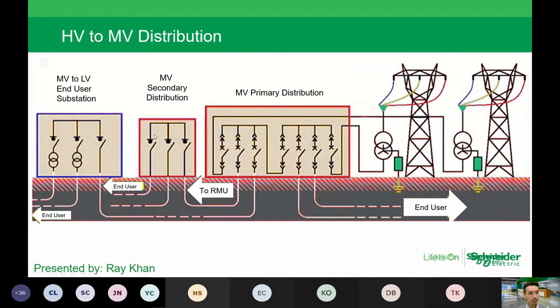From the secondary distribution, that is where sometimes we see requests for RMU deployment. RMU is suitable for much lower current ratings. The fault rating and the control scheme are also much simpler at this portion for the RMU. Once it goes into the final distribution, that's where we could add up at the LV end user substation as well.